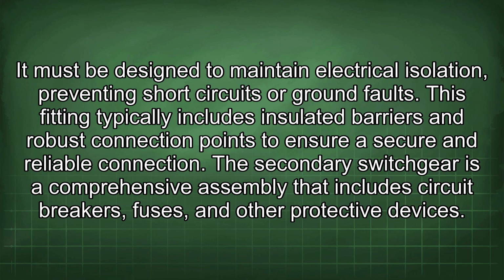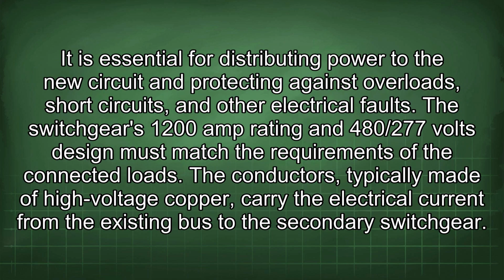The secondary switchgear is a comprehensive assembly that includes circuit breakers, fuses, and other protective devices. It is essential for distributing power to the new circuit and protecting against overloads, short circuits, and other electrical faults. The switchgear's 1200 amp rating and 480/277 volts design must match the requirements of the connected loads.